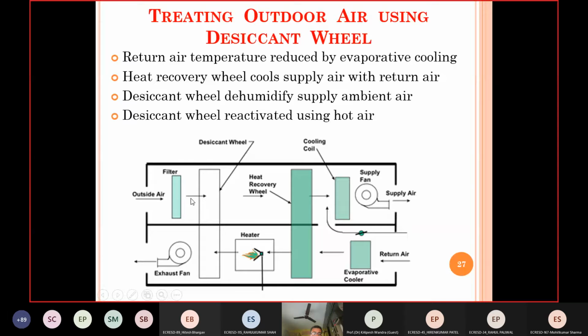So you're removing moisture from the outside air here and also cooling that air, and now it is supplied into the room to take care of either it reduces the enthalpy so that the conventional system has to take away less enthalpy, or if you dehumidify it to the required level, it can even take care of the latent load in the space. Okay. So this is energy recovery using the dedicated outdoor air system. Okay.